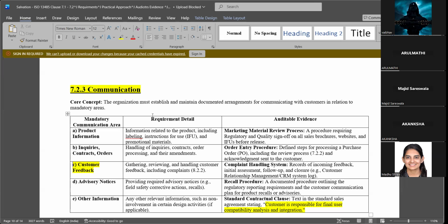Maybe some of you may not be aware; I think I shared it on WhatsApp, maybe you had read it or not. You need to report your complaints, adverse events, serious adverse events, any event, on the CDSCO medical device portal called Materiovigilance Programme of India. It is a portal opened by the CDSCO Medical Device Division. How many of you know this? For Europe they have EUDAMED, for the US they have MAUDE, and for India we have Materiovigilance for medical devices.